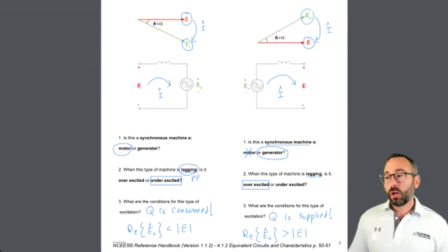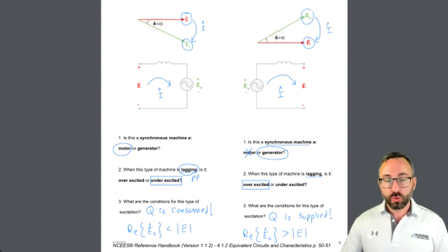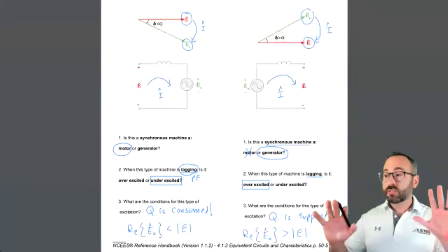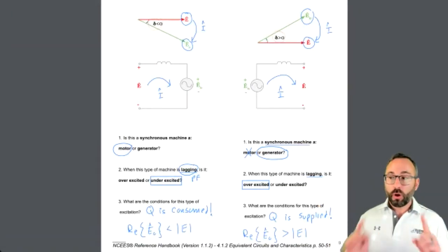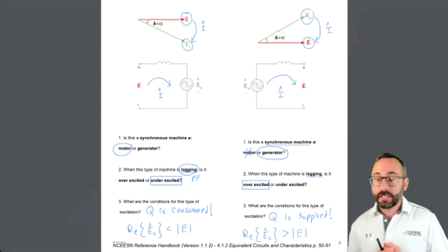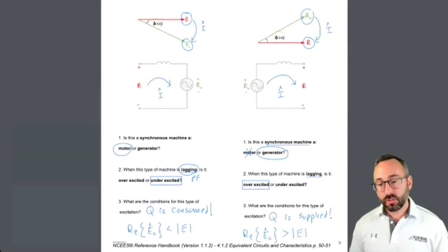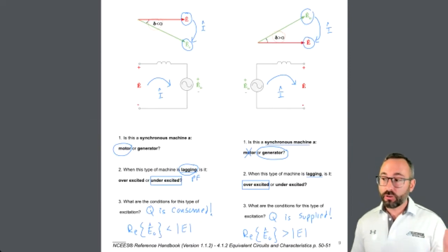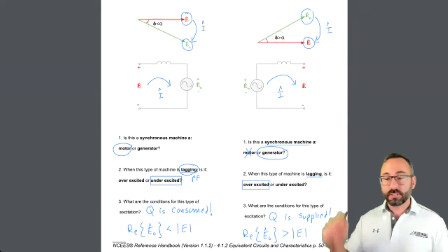Really quick: for an overexcited machine, whether it's a motor or a generator, this is always true - the real component of EO is greater than E, and Q is being supplied. For an underexcited synchronous machine, whether motor or generator, Q is being consumed, and the real component of EO is smaller than E. So those hold regardless of motor or generator. What changes is your lagging versus leading power factor in relation to the excitation. Now we've got a lagging motor being underexcited, and a lagging generator being overexcited.